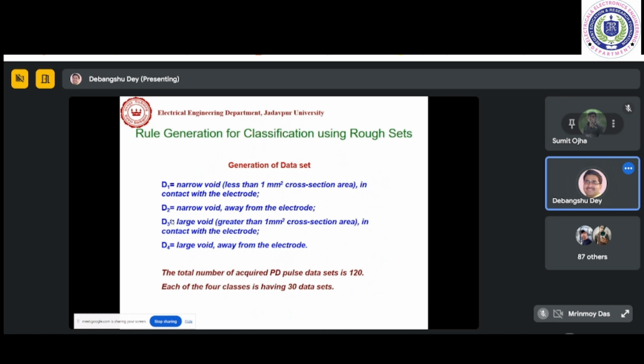These 4 classes are D1, D2, D3, D4. D1 is a narrow void. I'm keeping this simple, that's why only 4 classes; a more complex problem will have more classes. D1 is narrow void in contact with the electrode, D2 is narrow void away from the electrode, and D3, D4 are the large void, in contact and other. That means we are trying to locate the position of that particular partial discharge. If we can locate it, we can take measures to change the insulation at that position, so the partial discharge cannot lead to a deadly fault.